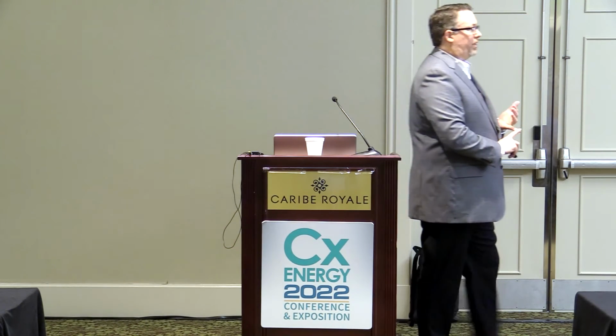What can impact it, right? I'm not going to put poor commissioning or poor TAB, we're going to assume everybody here has never had an issue with getting hot water temperatures consistently. But over time, and new buildings can also have an issue with startup and getting that system balanced properly. You guys spend a lot of time working on that. But as the building is operating and gets turned over to the owner, you see scale buildup happen. That's going to cause issues with your balancing valves.